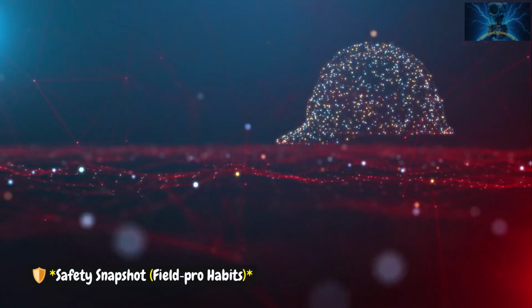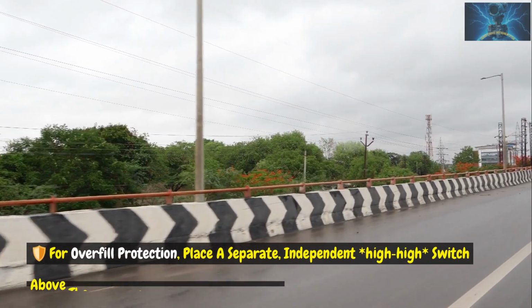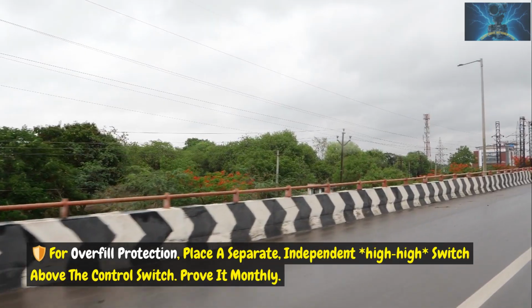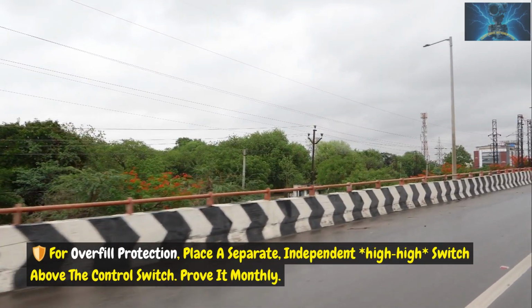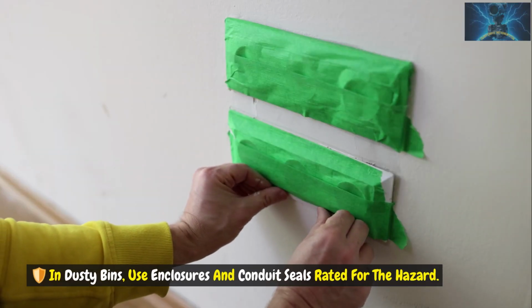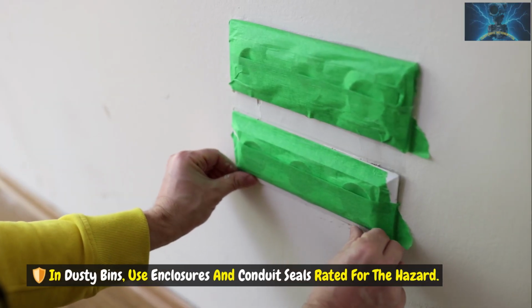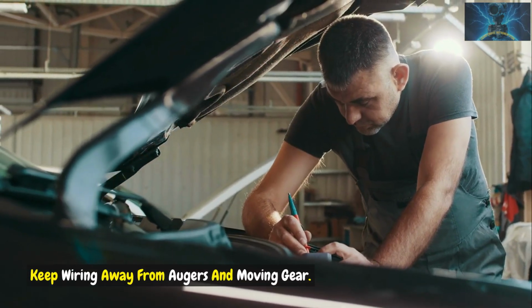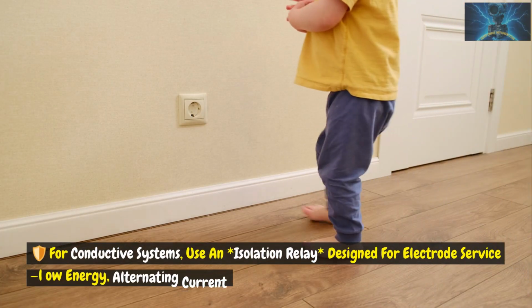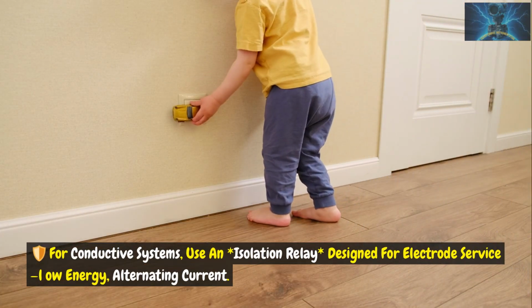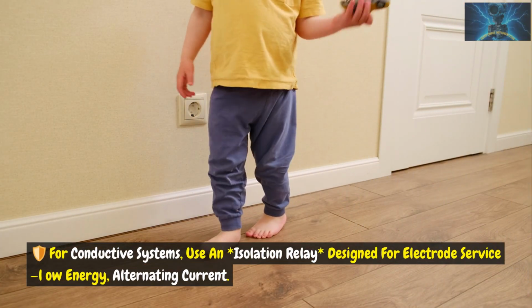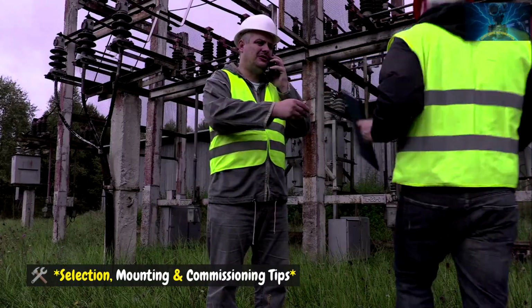Safety snapshot: Field Pro habits. For overfill protection, place a separate, independent, high-high switch above the control switch. Prove it monthly. In dusty bins, use enclosures and conduit seals rated for the hazard. Keep wiring away from augers and moving gear. For conductive systems, use an isolation relay designed for electrode service: low energy, alternating current.